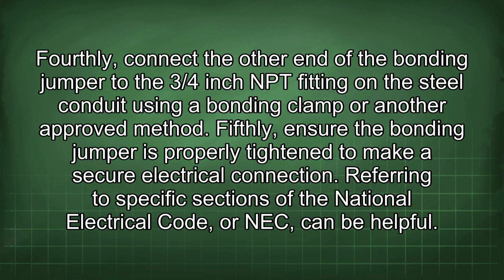Fourthly, connect the other end of the bonding jumper to the 3/4" NPT fitting on the steel conduit using a bonding clamp or another approved method. Fifthly, ensure the bonding jumper is properly tightened to make a secure electrical connection. Referring to specific sections of the National Electrical Code, or NEC, can be helpful.